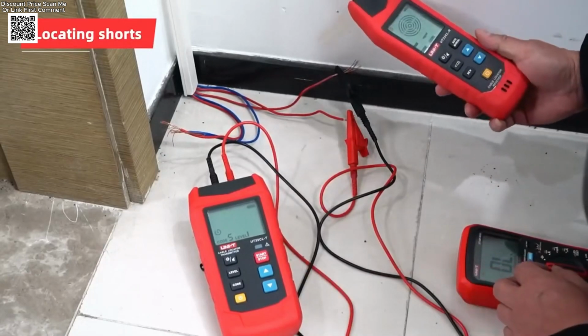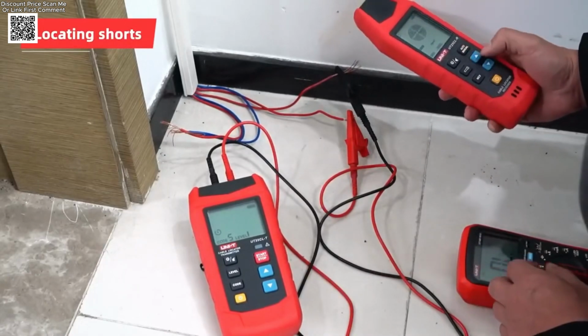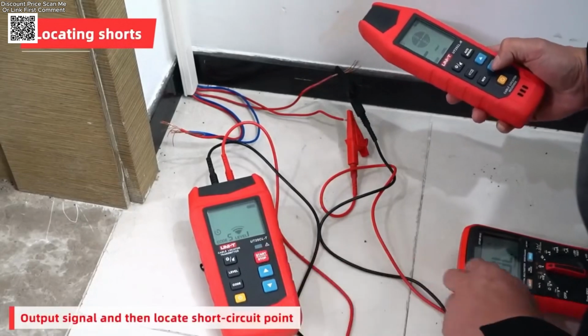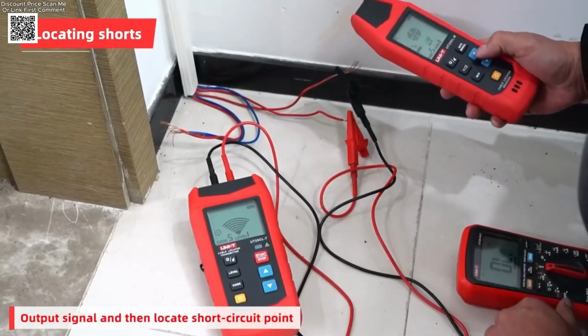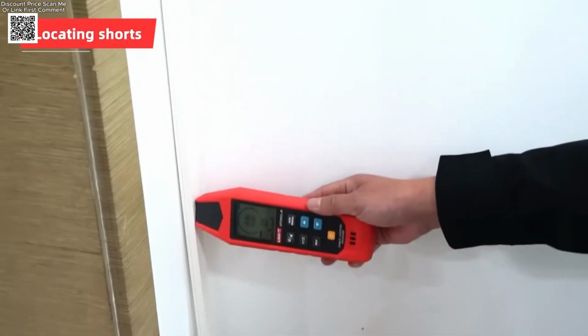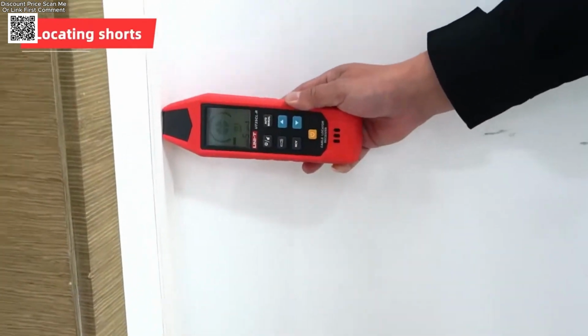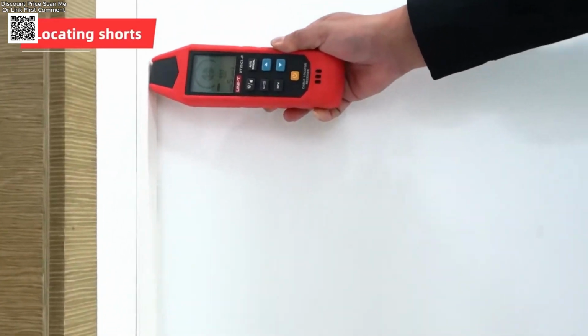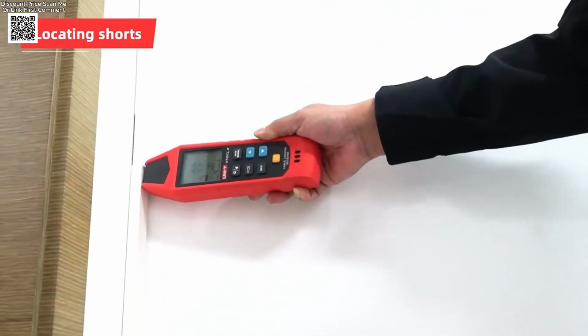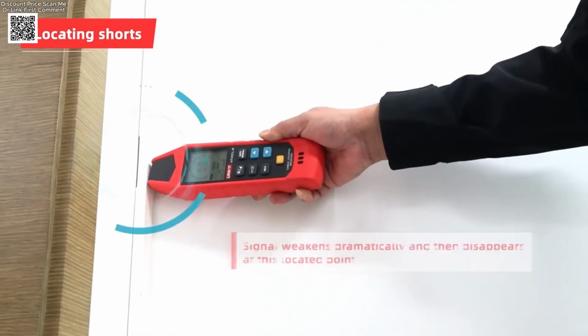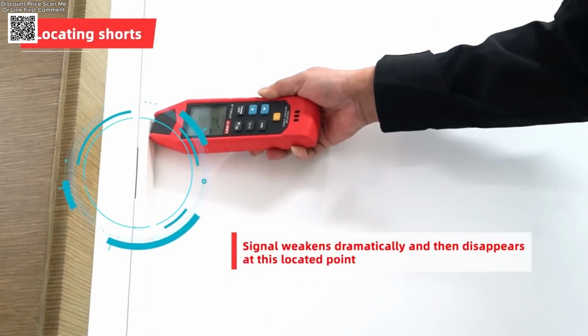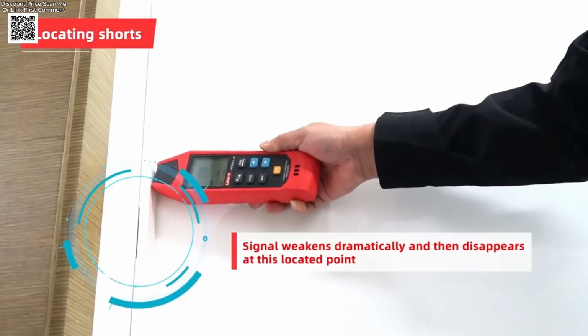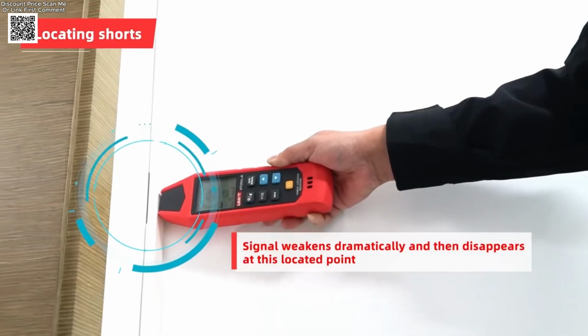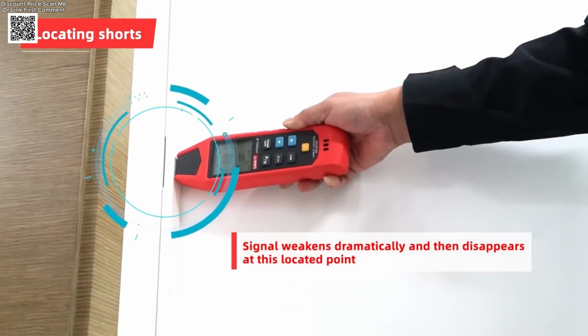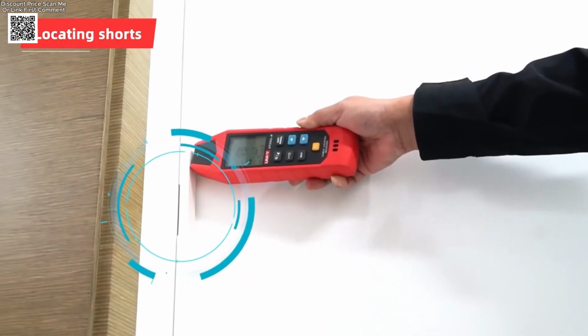The transmitter is the signal source. You connect it to the cable under test with the included leads or clips. There are 3 levels of adjustable signal strength. The lower levels help avoid false positives from nearby lines, while the higher level is useful for long runs or deeper burial. You can also pick from 8 coded signal channels. That is helpful in multi-core cables or in buildings where several technicians are tracing at the same time. One receiver can recognize up to 8 different transmitters by code.